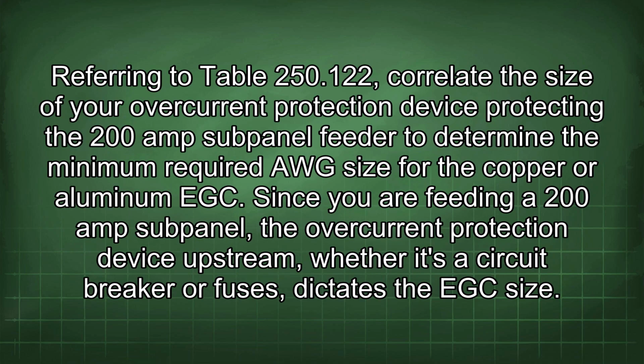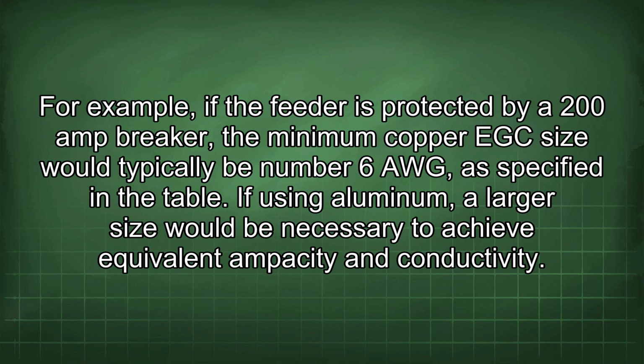Referring to Table 250.122, correlate the size of your overcurrent protection device protecting the 200 amp subpanel feeder to determine the minimum required AWG size for the copper or aluminum EGC. Since you are feeding a 200 amp subpanel, the overcurrent protection device upstream, whether it's a circuit breaker or fuses, dictates the EGC size. For example, if the feeder is protected by a 200 amp breaker, the minimum copper EGC size would typically be number 6 AWG, as specified in the table. If using aluminum, a larger size would be necessary to achieve equivalent ampacity and conductivity.